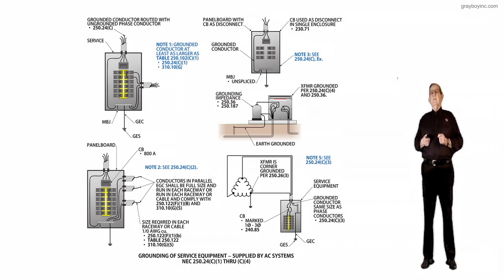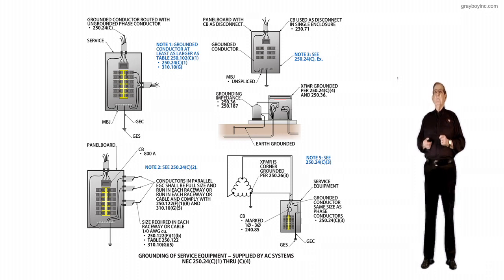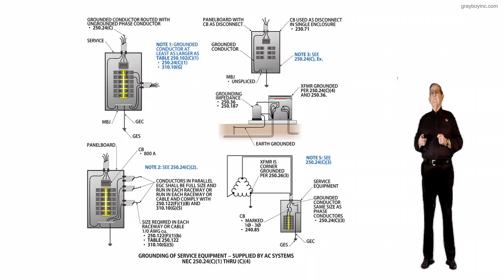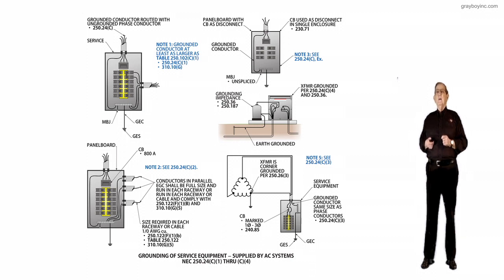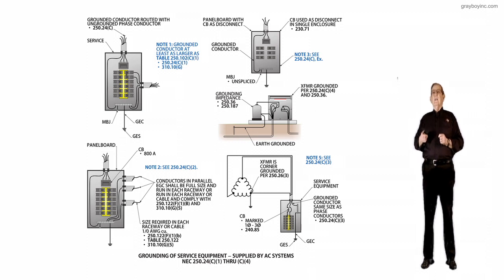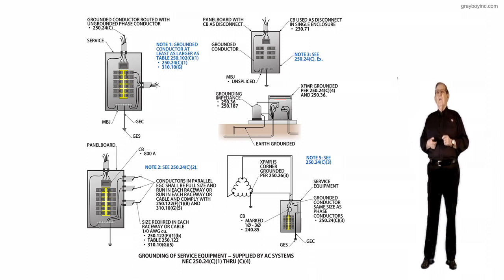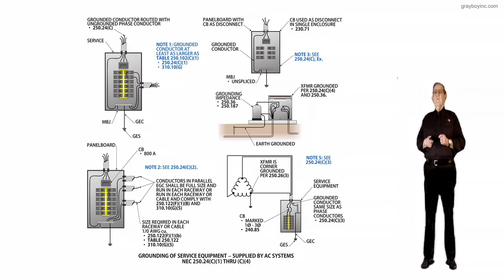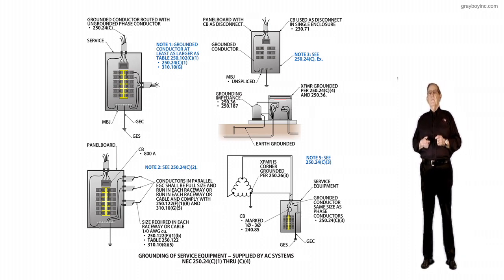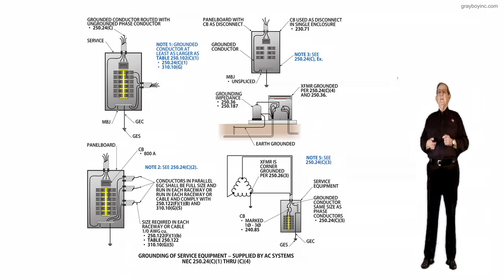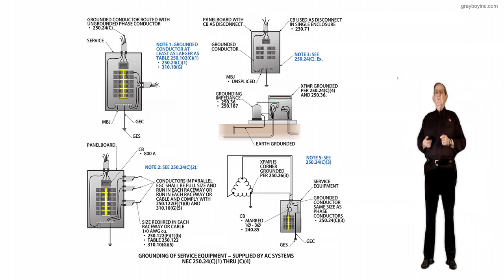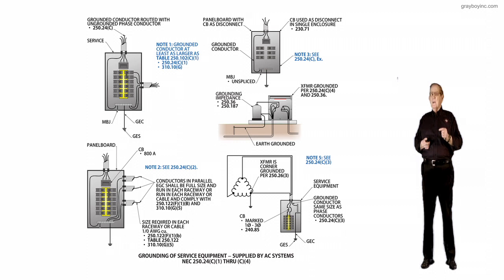Let's review the right-hand side up at the very top of that panel board. Notice we have an unspliced bonding jumper. We connect that bar to ground. All your neutrals and equipment grounds are connected there, and the grounded conductor connects to that bar and is routed back to the grounded transformer, if it's service equipment and so forth. And then the illustration right below it, notice it's earth grounded through a high impedance grounding system that fully complies with 250.36 or 250.187 depending upon the voltage. But the transformer is grounded whether it's customer owned or owned by the utility.